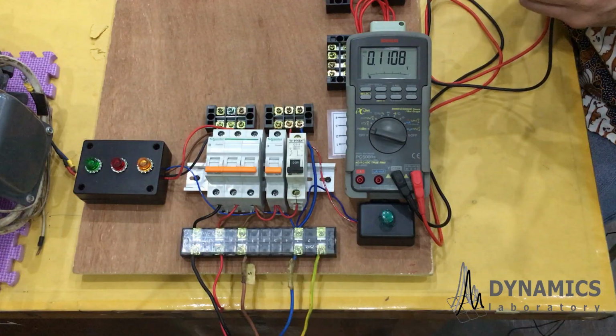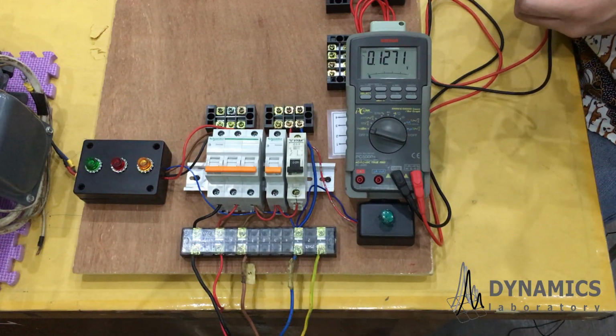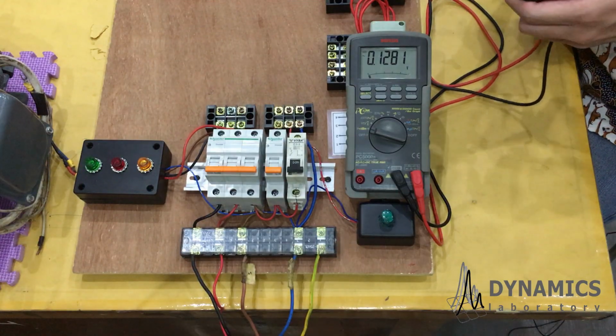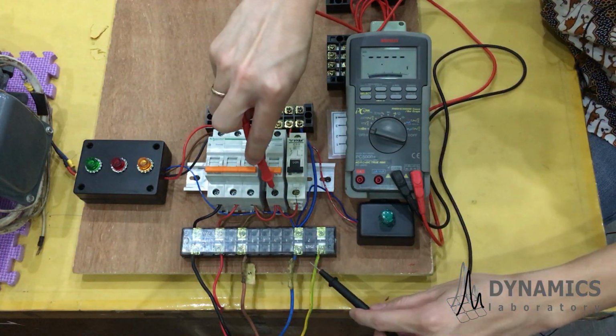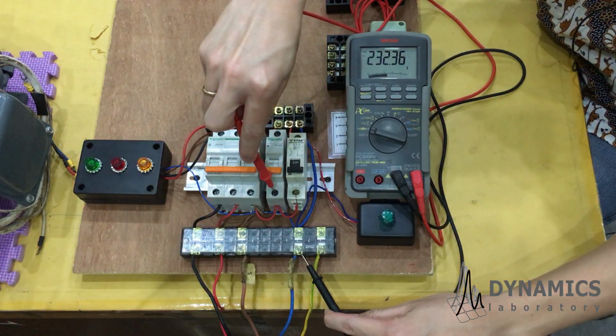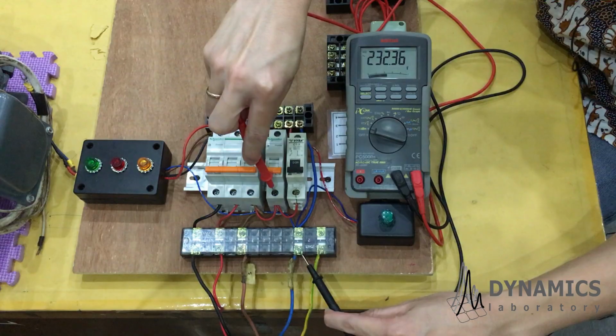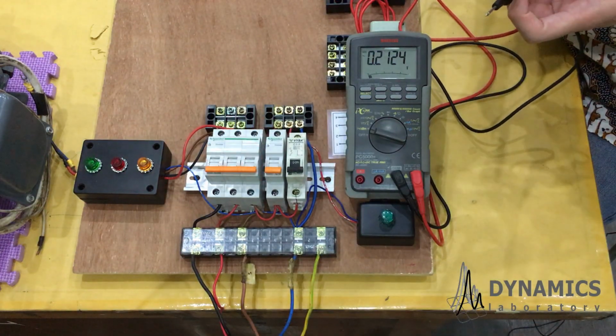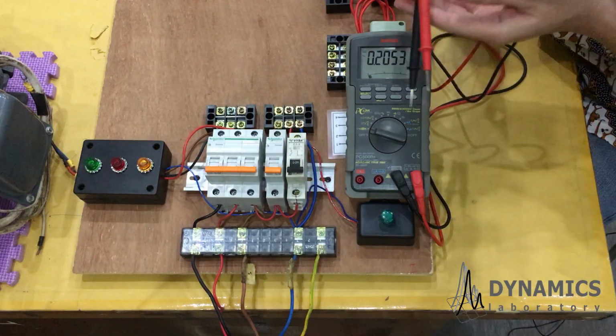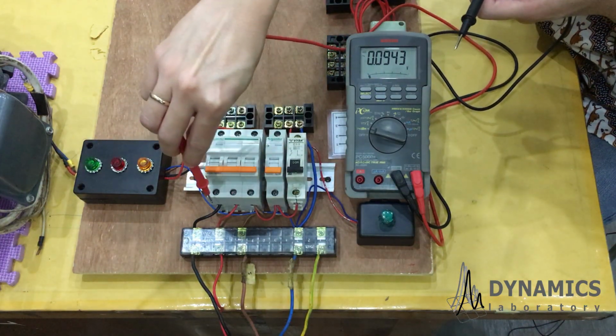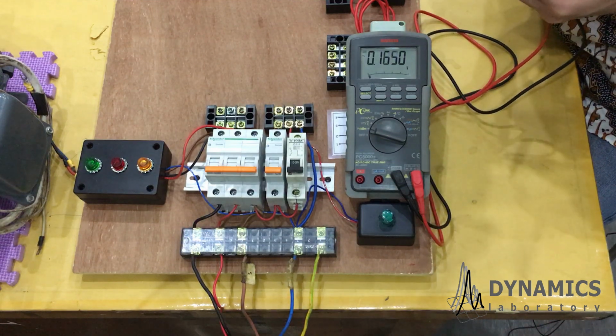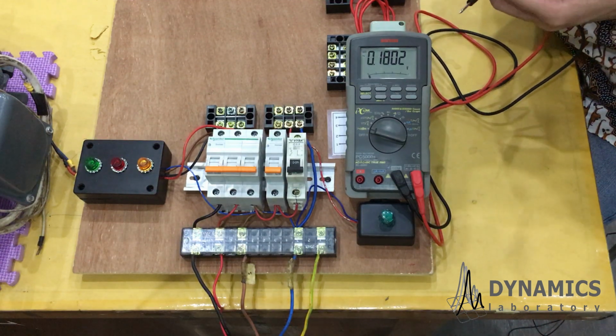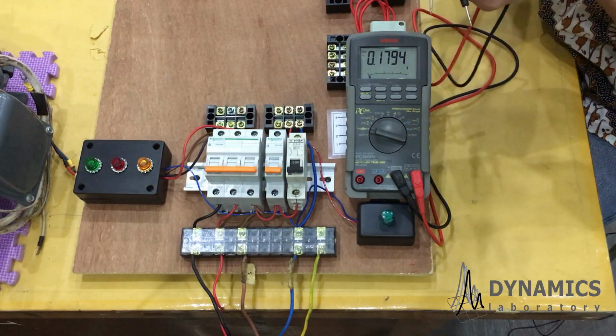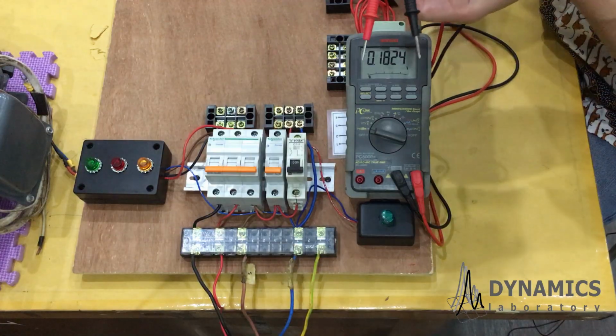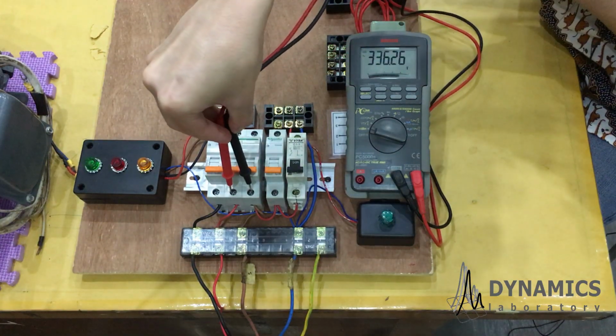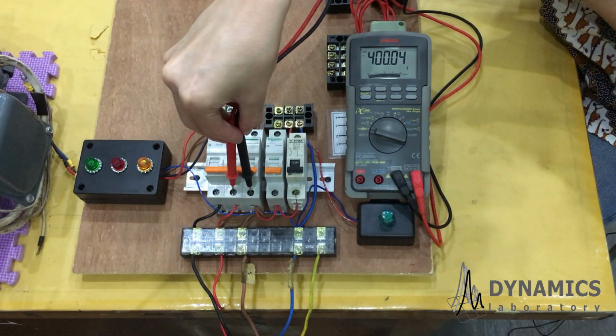Let's start the practicum. We start the practicum by measuring one-phase and three-phase grid voltage. First, one-phase line to neutral. It shows 232 volt. Move to three-phase grid voltage. We call this brown, red, and black cable as R, S, and T voltage line. That's why first we want to measure line to line, R to S.